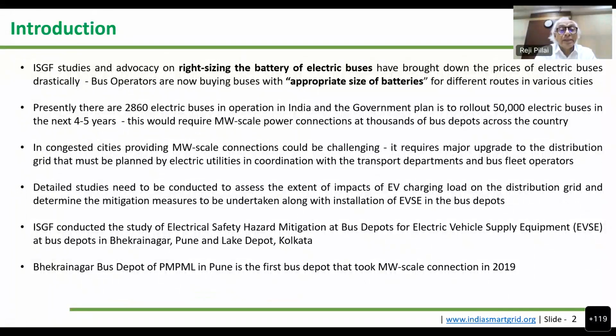And they never looked at a megawatt scale, and they don't understand the complication of running a megawatt scale power distribution system within a bus depot. Electric utilities never considered bus depots to be a major customer in the past, because they always took a 30 kilowatt or 50 kilowatt connection. So now all of a sudden they are coming and asking for a 5 megawatt, 10 megawatt electricity connection. This is something which is happening for the first time.